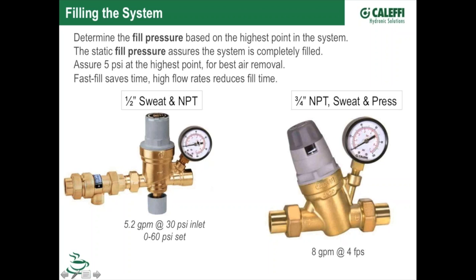It's got a pressure gauge on so you can monitor for leaks in the system, fill it up, shut off the valve or shut off an isolation valve here, keep an eye on your gauge for a couple hours or a day. It'll be a troubleshooting device as well as an indication that you've filled your system to the proper pressure.